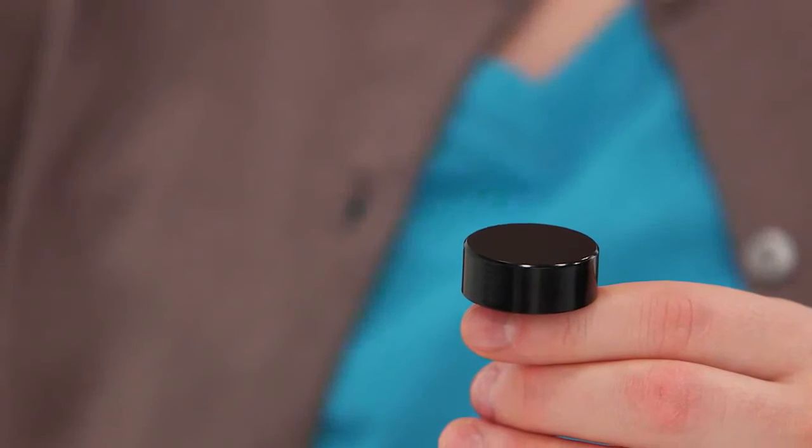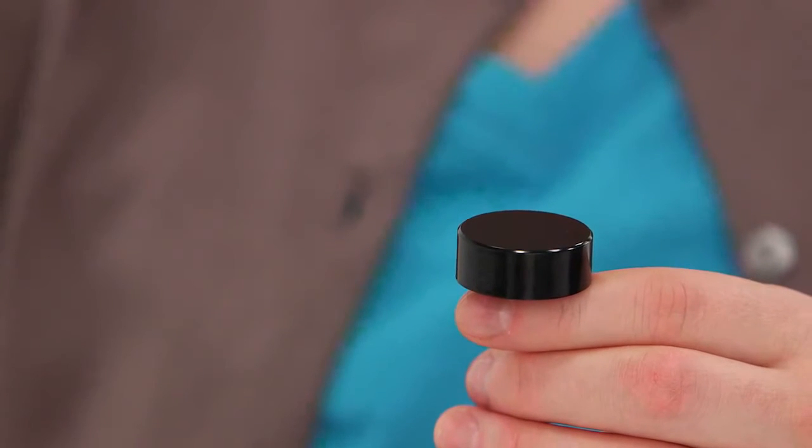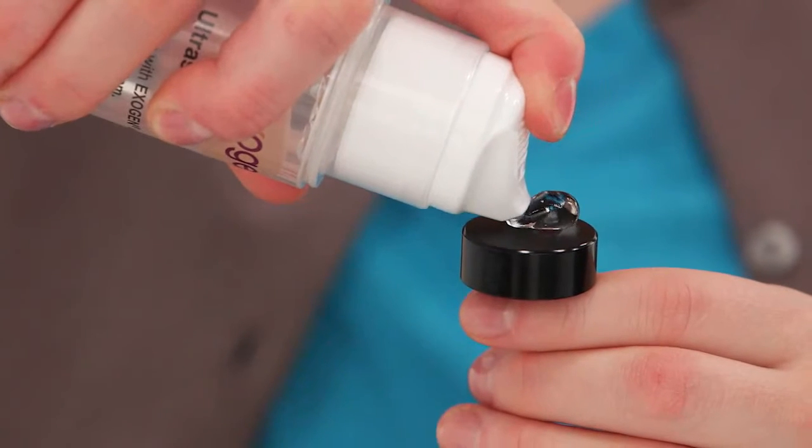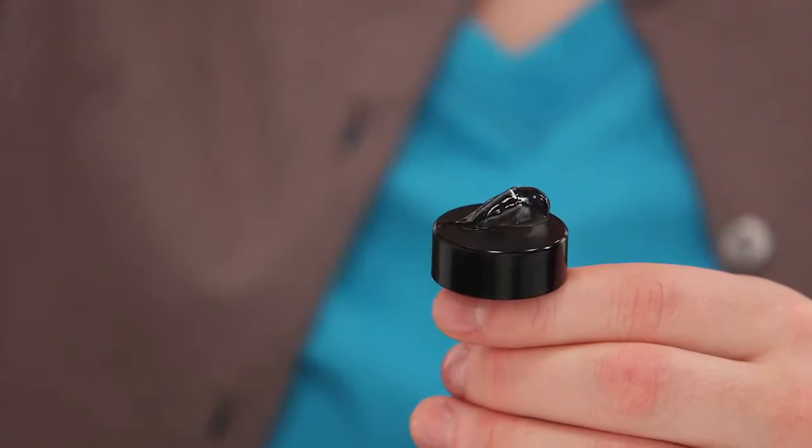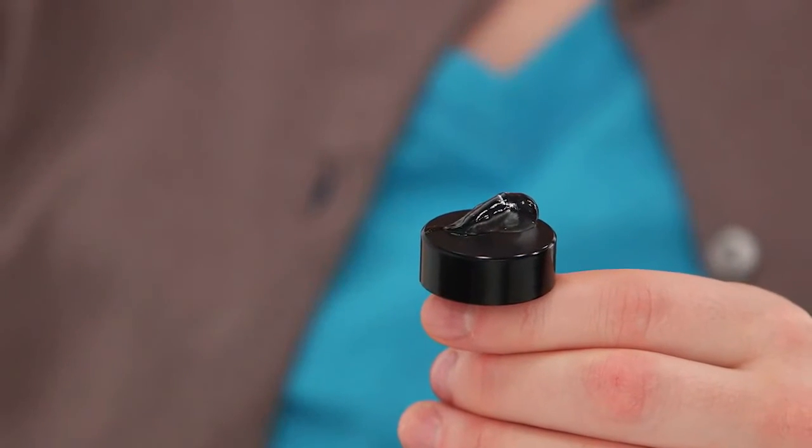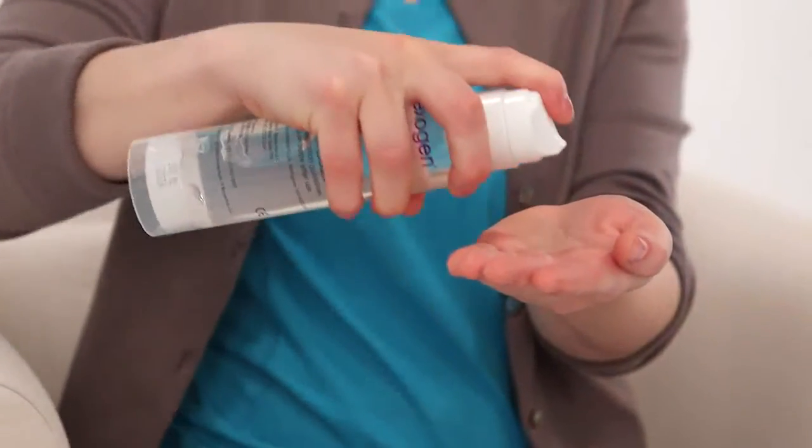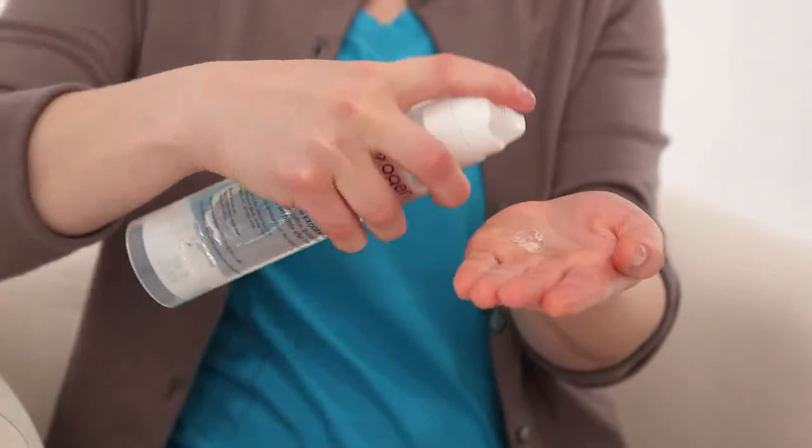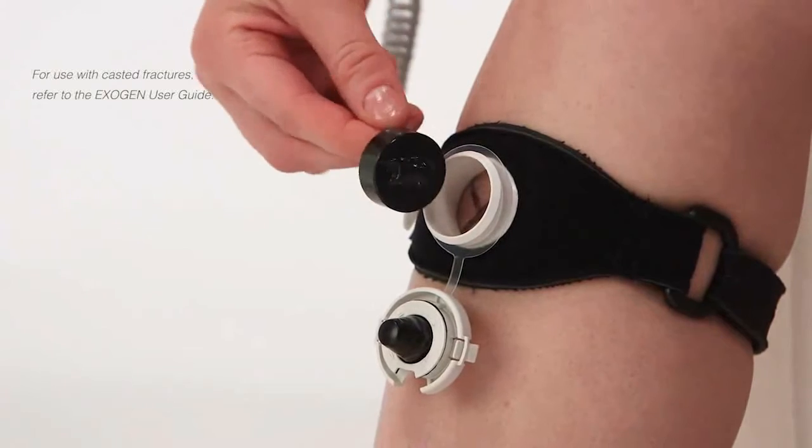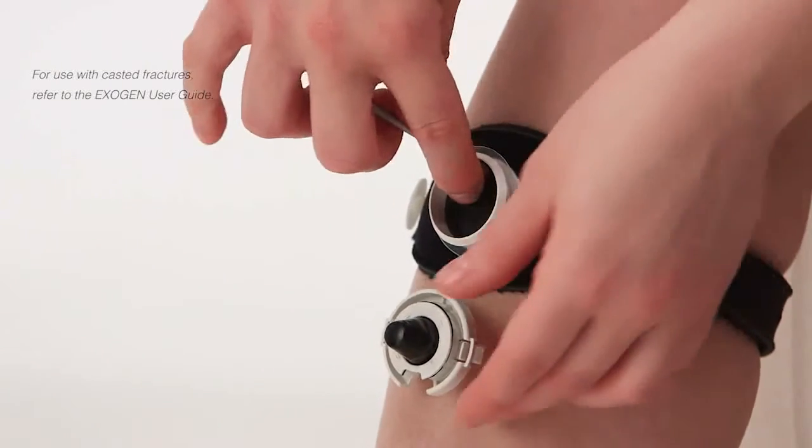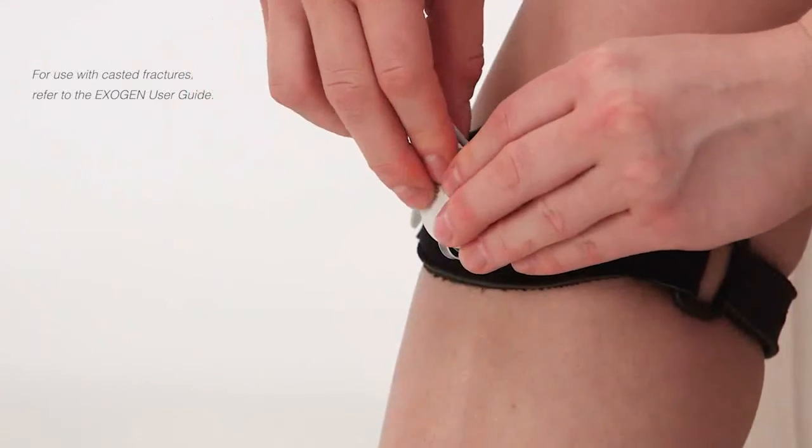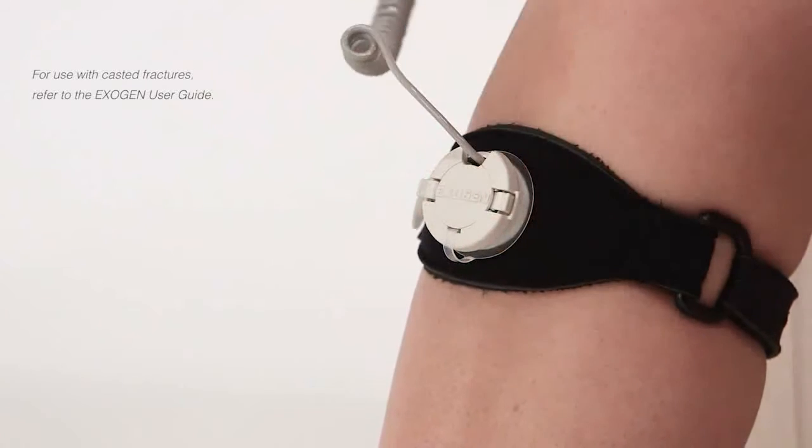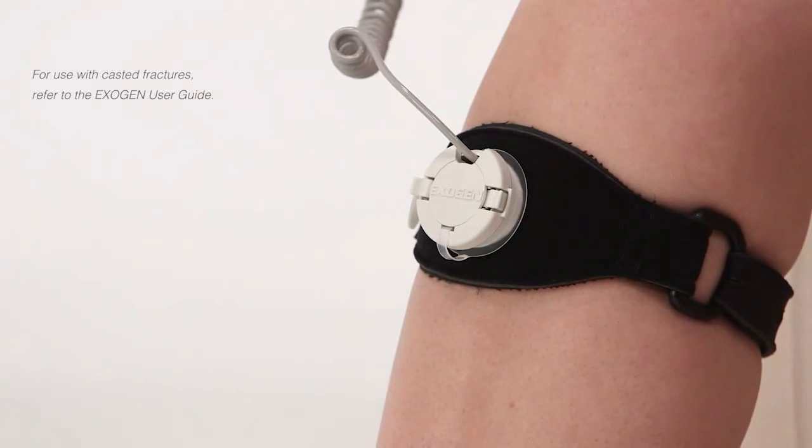To apply the gel, hold the transducer with the cord down and smooth side facing up. Press down on the gel bottle nozzle to deliver one full pump of gel onto the transducer. If this is the first time using the gel bottle, it may take several pumps before the gel is expressed. Place the transducer, gel side down, into the port so the gel is touching the skin over your treatment site. Place the transducer cord into the notch so the cord comes out of the cap and snap it shut.